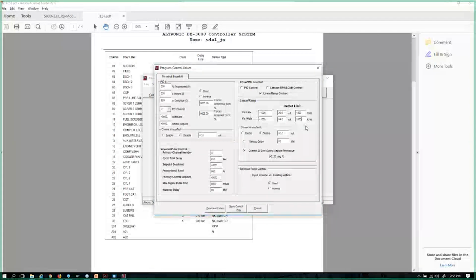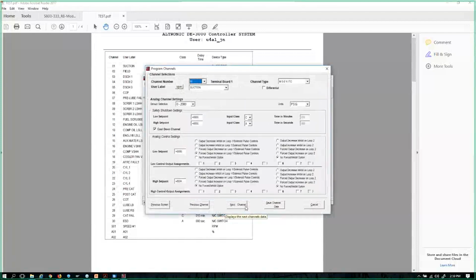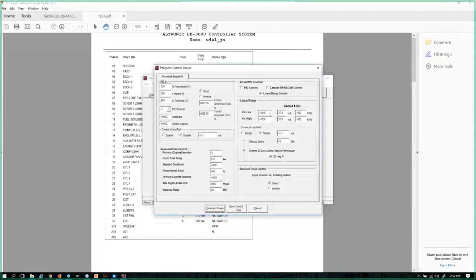Did that answer your question? Yes, a little bit, but the question is if you rise to the higher pressure, then if the pressure comes higher, how do they go? It's easy if I show you with a picture, but you go in a ramp, you rise, and then you maintain the value in the maximum RPM. Because we have one problem: when the controller gets to the maximum value, it goes to the lower RPMs.